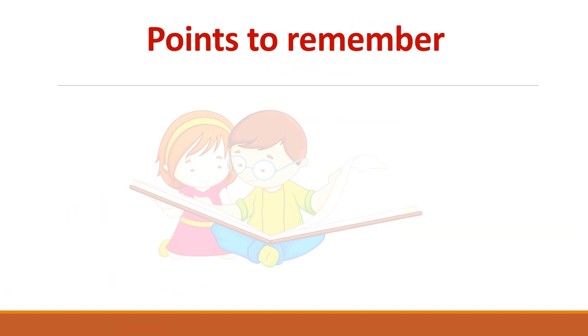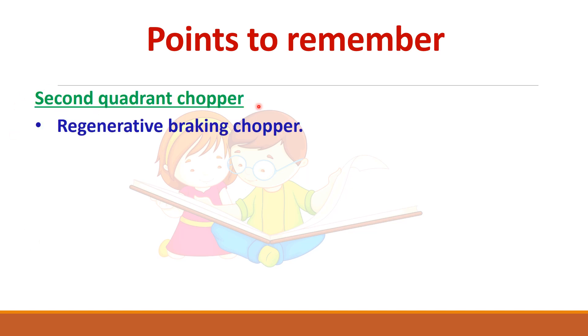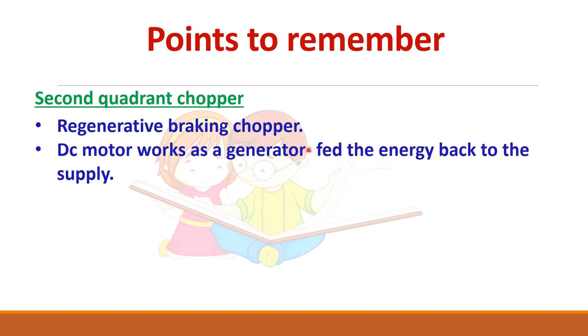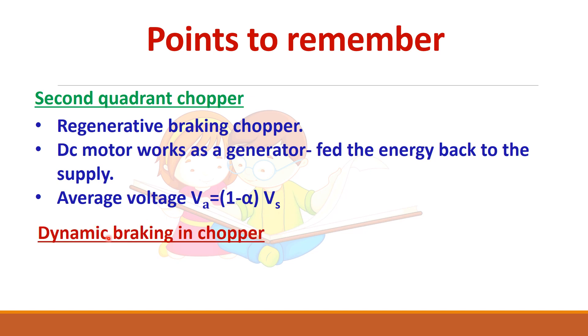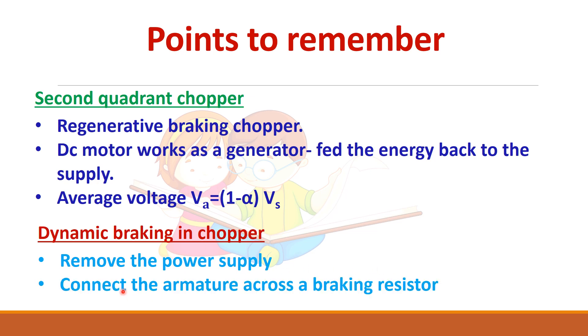To summarize: this is a second quadrant chopper, also called a regenerative braking chopper. Here the motor works as a generator and feeds energy back to the supply, and the average voltage is given by (1 − α)·Vs. For dynamic braking, the power supply is removed and a braking resistor is connected across the armature.